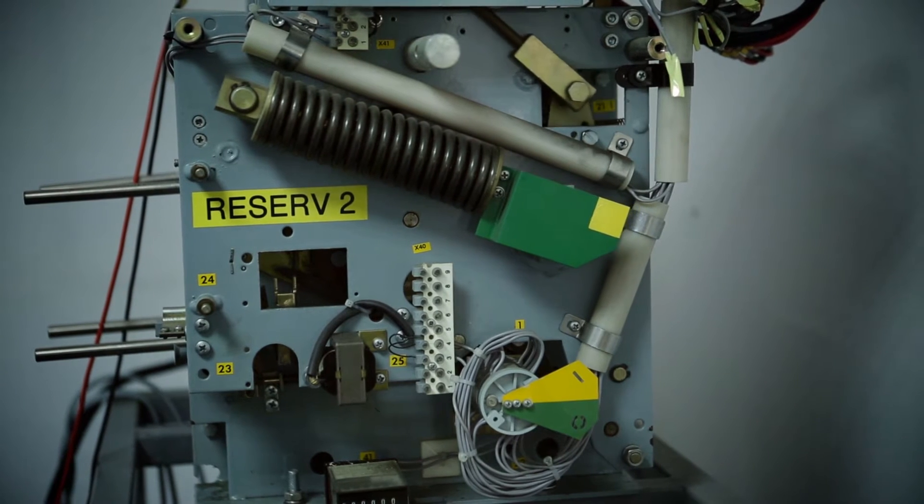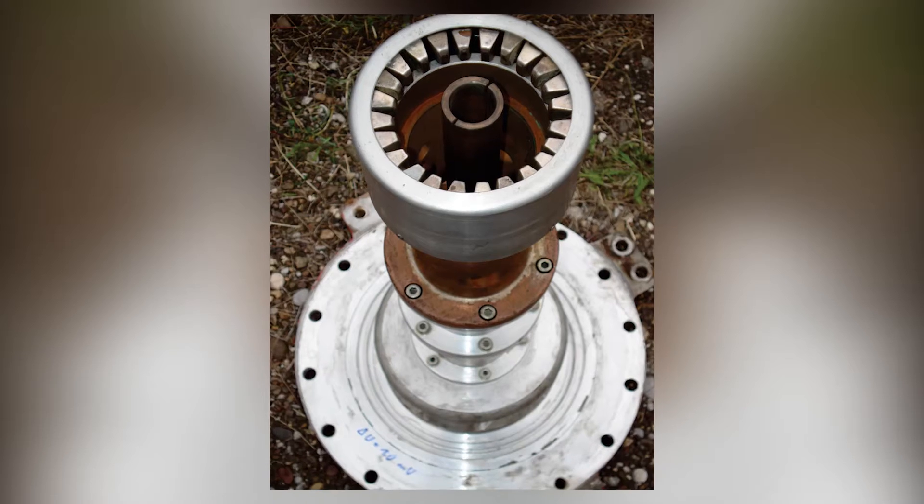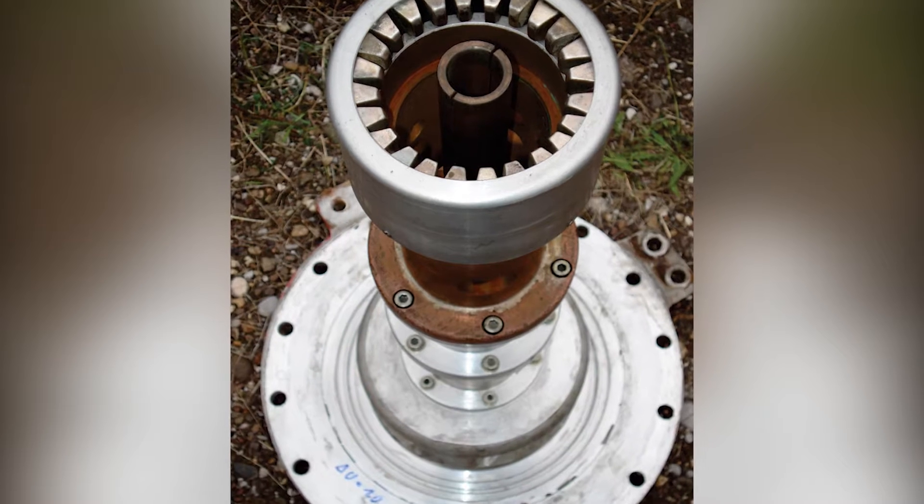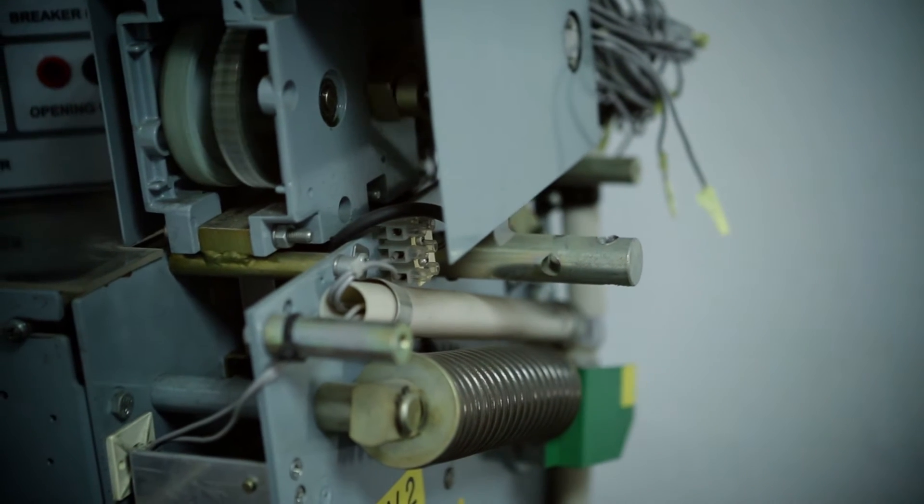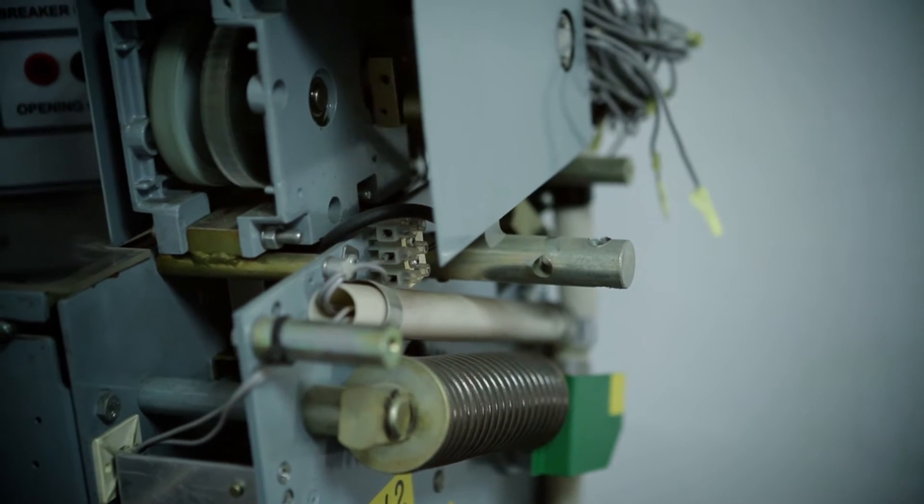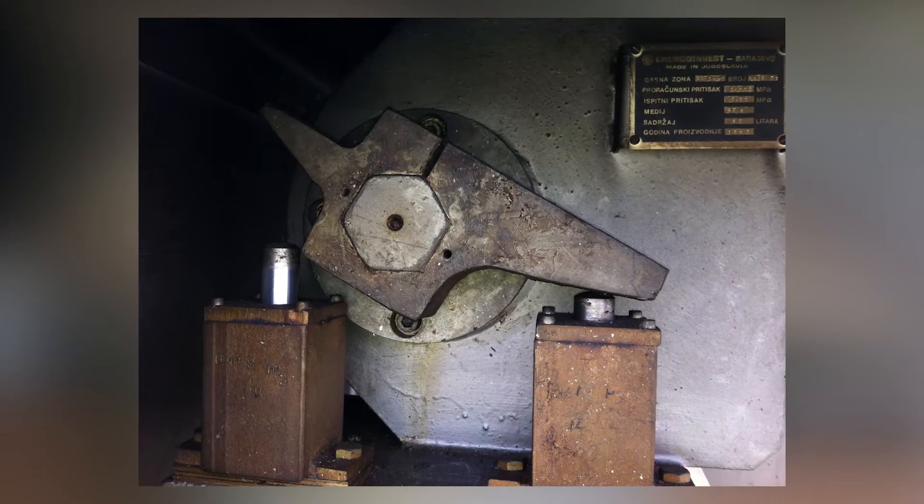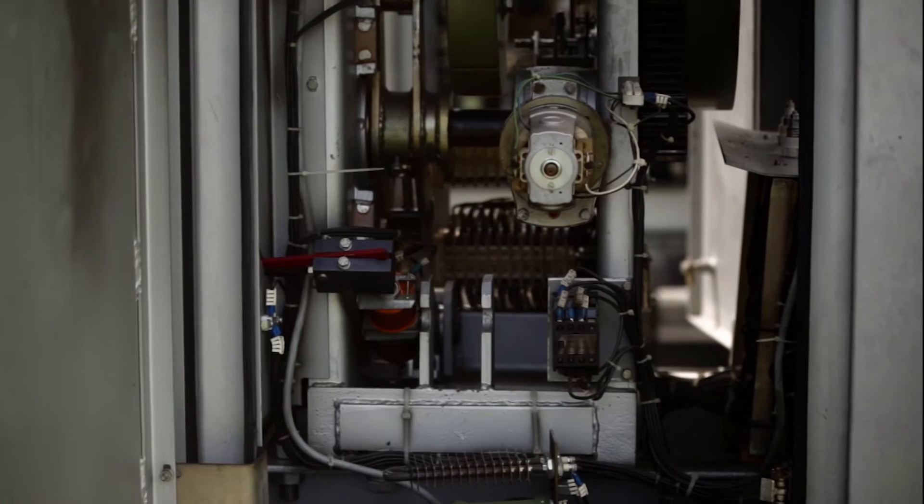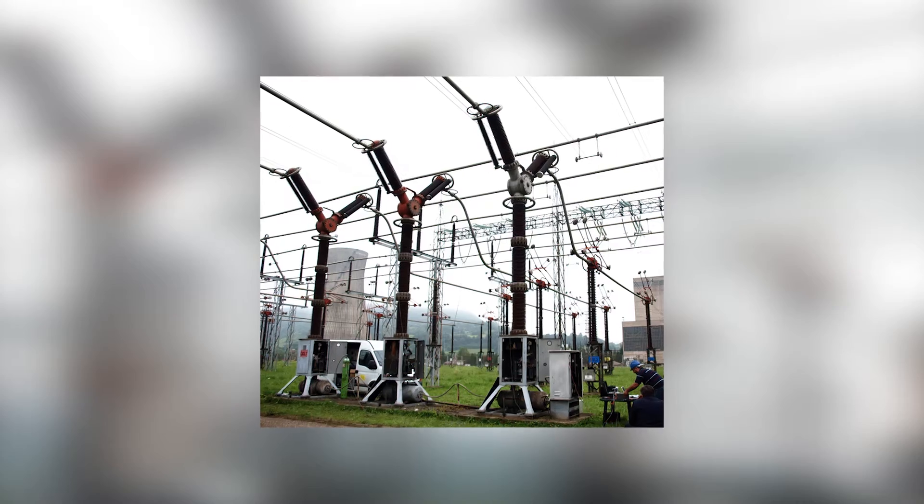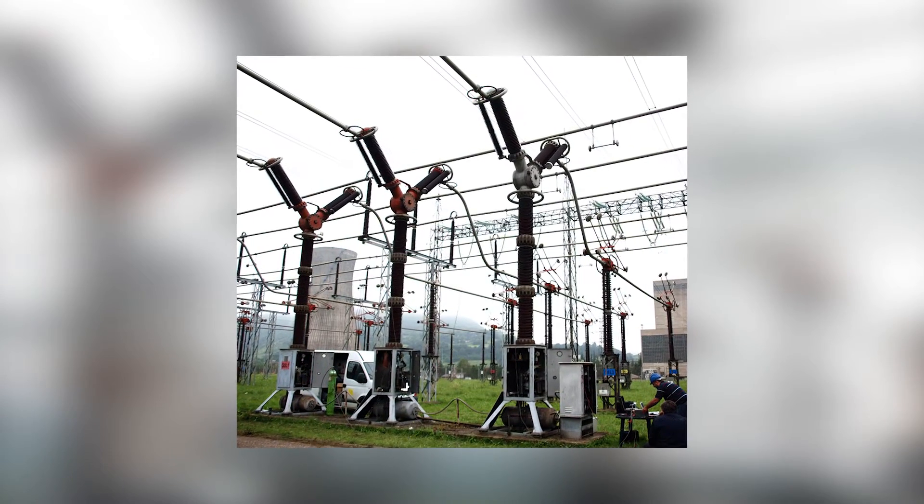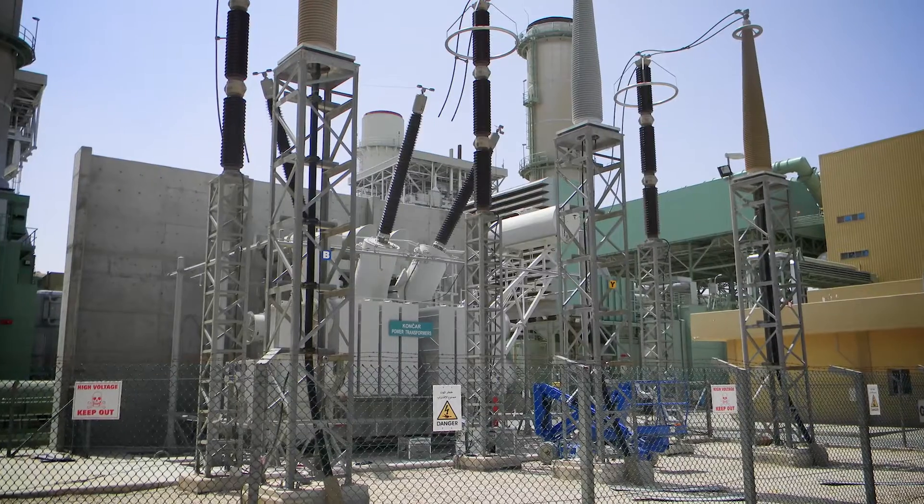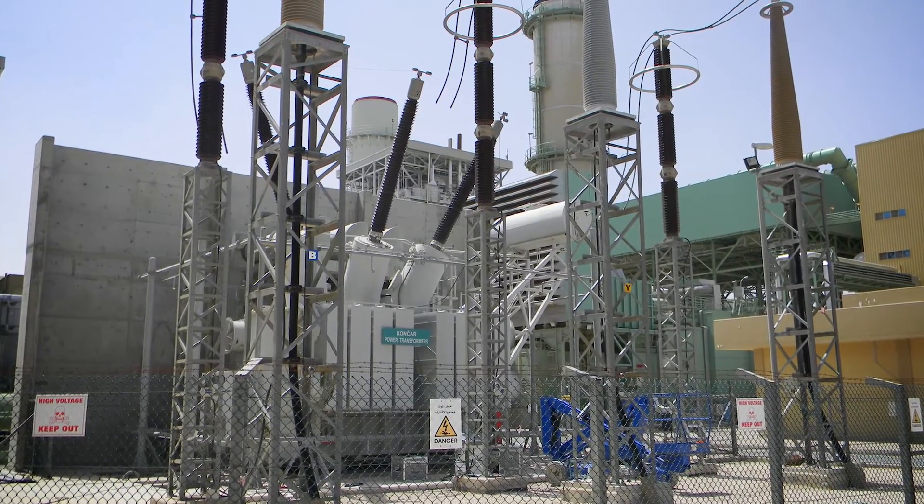There can be various causes of circuit breaker failure: increased resistance of a main circuit, friction and wear of moving parts, insufficient storage of driving energy in operating mechanism, improper damping devices. Faults can also occur in electrical control circuits. All these defects can cause a circuit breaker not to operate properly when it is needed the most, such as during a short circuit fault.